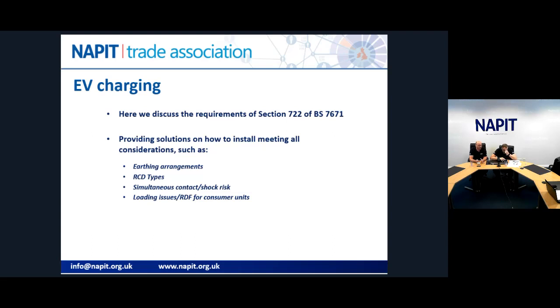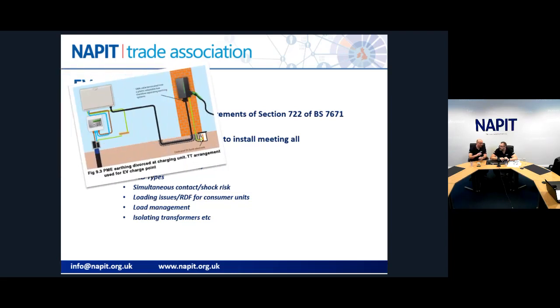Loading issues - there's a lot to consider here. We give all the rated diversity factors for consumer units, so if you're putting in a heavy constant load like EV, you know how to set up your consumer unit so there's no infringement on the manufacturer's instructions. We talk about load management and how different charging equipment can deal with that, and we're also looking at isolating transformers as a protective measure. You've got sample illustrations clearly showing how to separate earthing systems, etc.